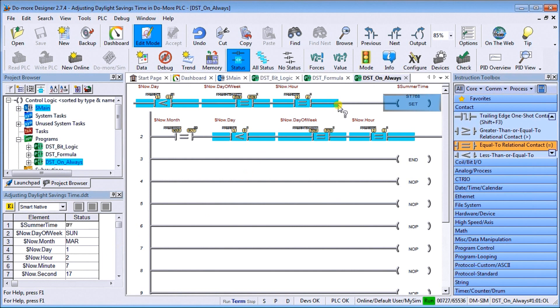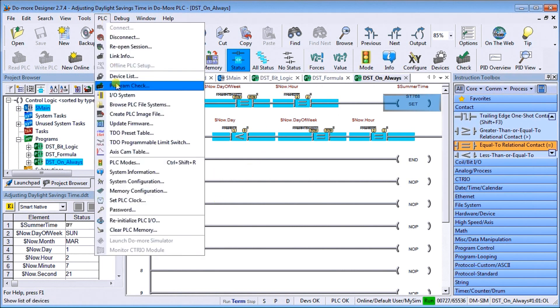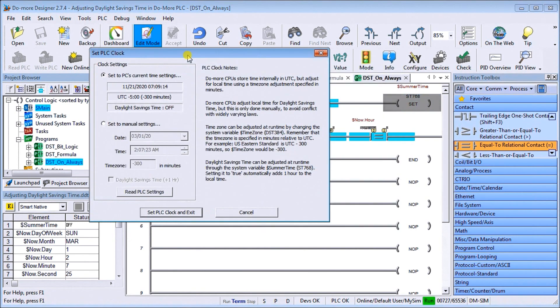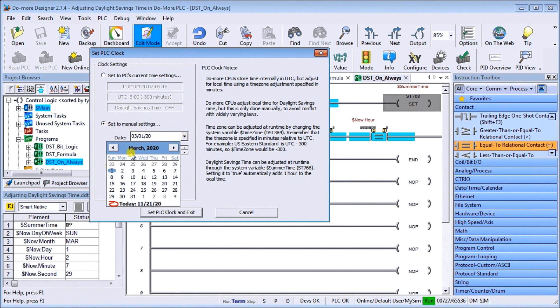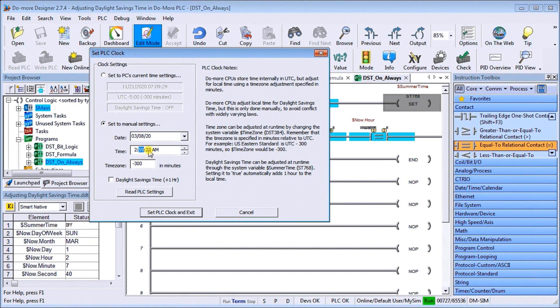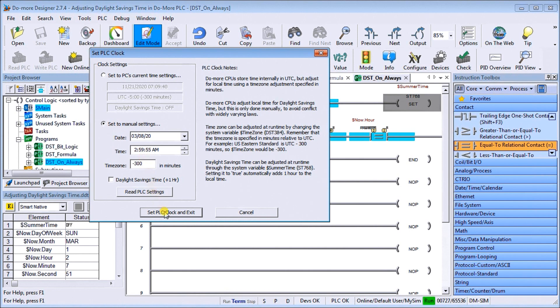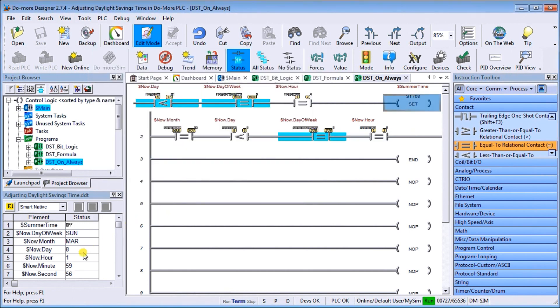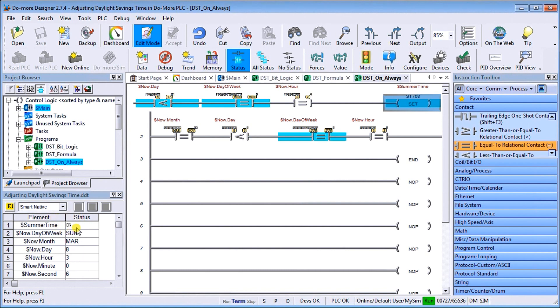Now what I've done is adjusted our data view, and our data view actually will show us what the current setting is right now. Let's actually turn that summertime bit on by going into the PLC. We can go set PLC clock, and when we do that we can go down to manual settings. We see that we're in March, let's go the second week of March which would be the eighth. Then we'll set this for 2:59:55. Why that is, is because remember the summertime setting is going to subtract an hour, so we'll get 1:59:55 when we put this in the PLC.